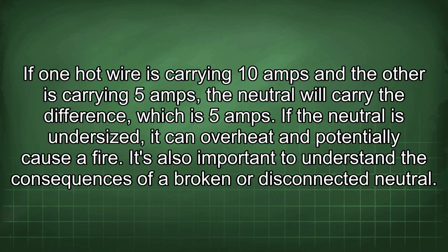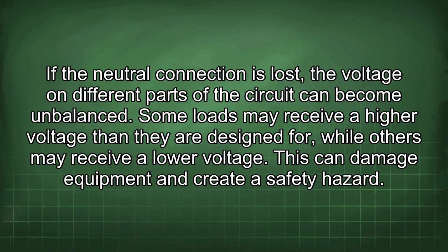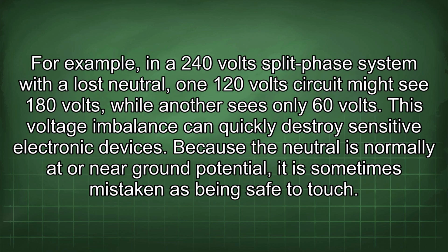It's also important to understand the consequences of a broken or disconnected neutral. If the neutral connection is lost, the voltage on different parts of the circuit can become unbalanced. Some loads may receive a higher voltage than they are designed for, while others may receive a lower voltage. This can damage equipment and create a safety hazard. For example, in a 240 volt split-phase system with a lost neutral, one 120 volt circuit might see 180 volts, while another sees only 60 volts. This voltage imbalance can quickly destroy sensitive electronic devices.